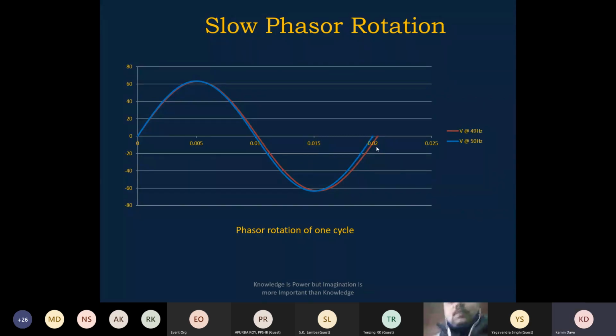Let us say the frequency is 49.9 hertz during a load condition, and that changes to 49.7 during a fault condition. In that case, we need to understand whether the equipment is capable of measuring such phasor rotation or not. I mean, whether frequency tracking is there to track the correct frequency, whether the frequency is 49.7.